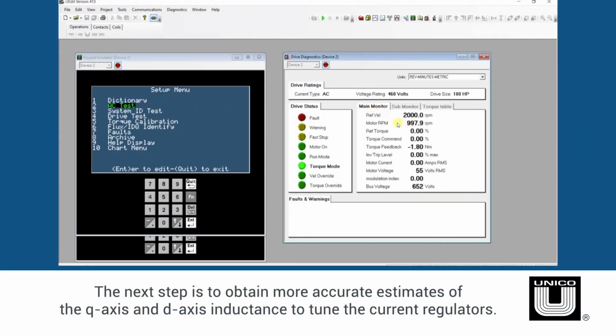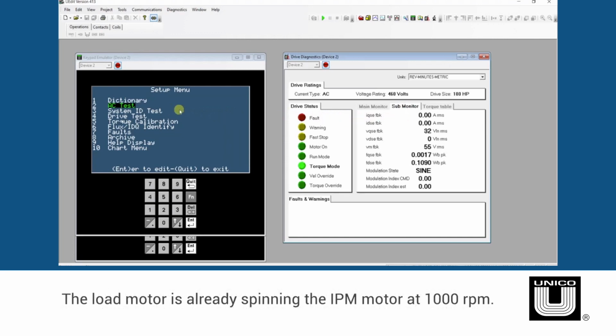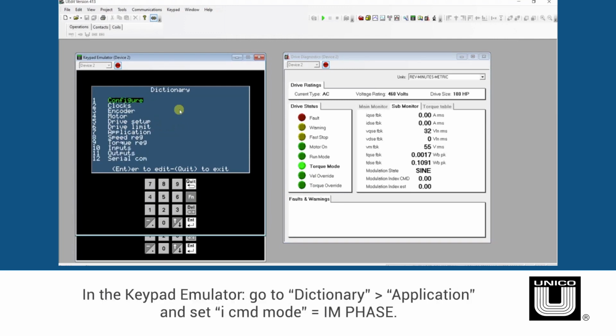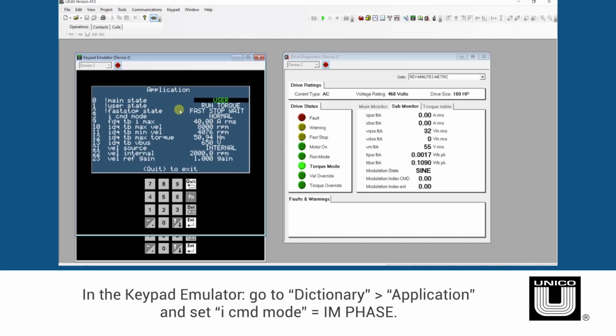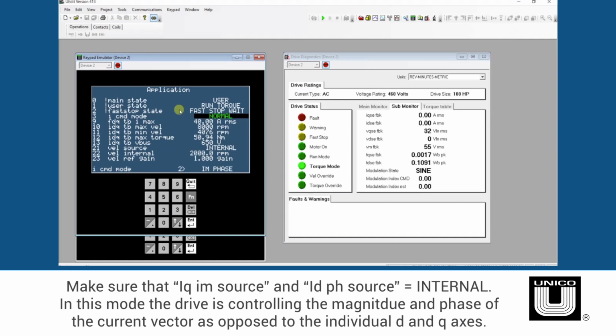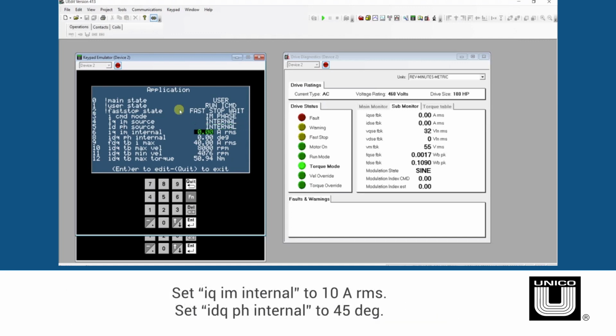The next step is to obtain more accurate estimates of the Q-axis and D-axis inductance to tune the current regulators. The load motor is already spinning the IPM motor at 1000 RPM. From the keypad emulator, go to Dictionary, Application, and set I command mode equal to IM phase. Make sure that IQ IM source and ID PH source equals internal. In this mode, the drive is controlling the magnitude and phase of the current vector as opposed to the individual D and Q axes. So set the internal current magnitude equal to 10 amps RMS and the internal current angle equal to 45 degrees.